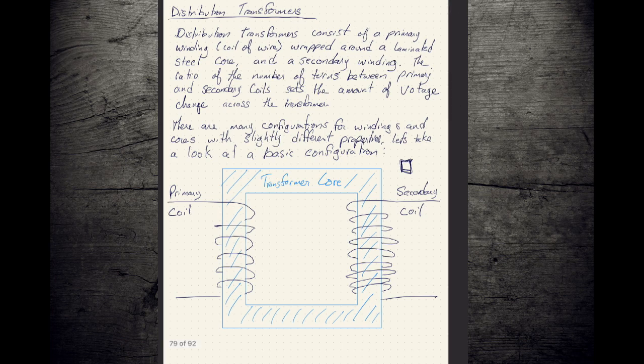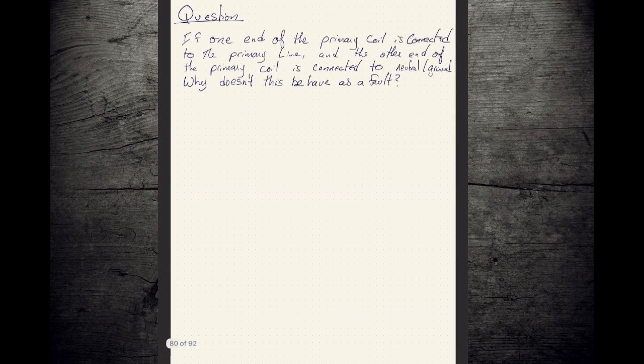We talked about transformer faults last week, and a fault occurs whenever you have your primary line and it connects either to another primary line or gets tied to neutral or ground. So anytime you take a piece of wire and you hook it up from your primary side to your ground or your neutral, that's a short circuit. We saw what happened when we got short circuits. The current went to the moon.